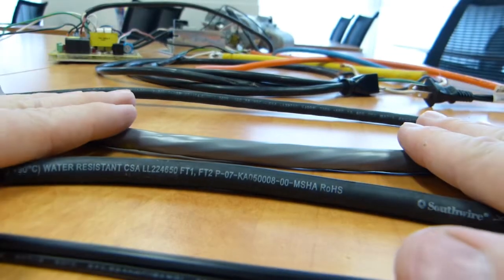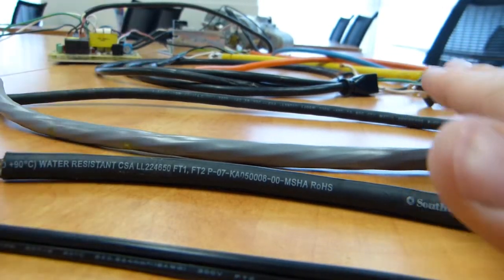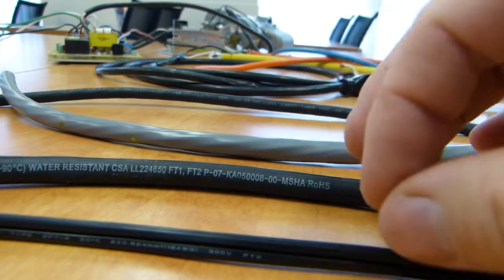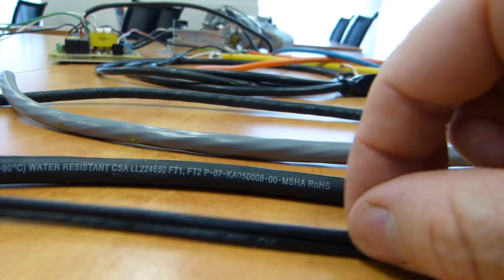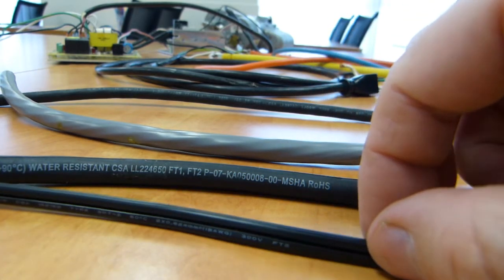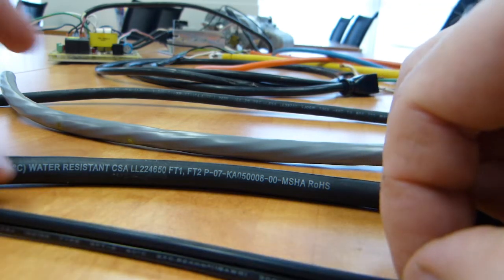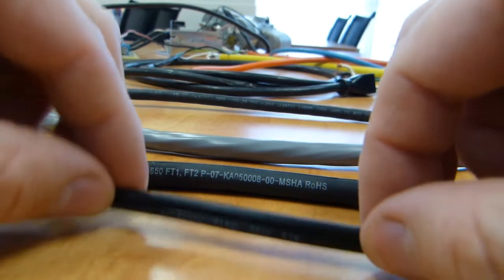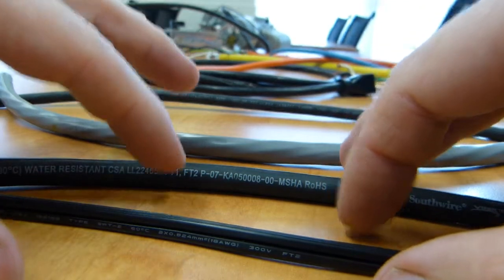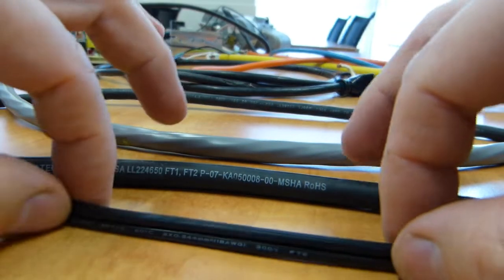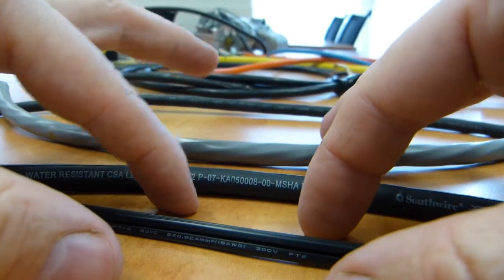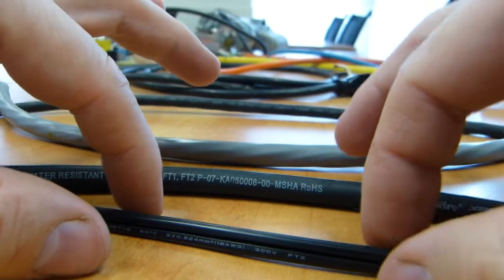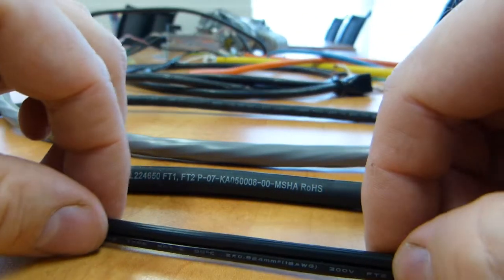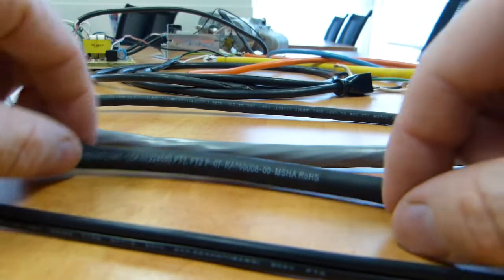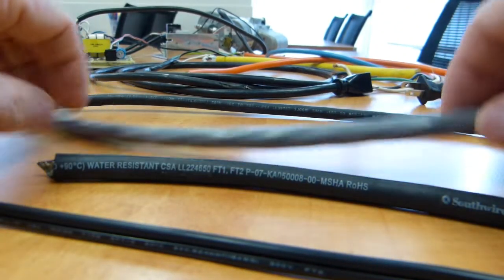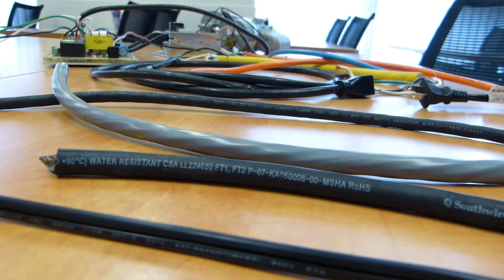So like I said, these numbers are about safety. What kind of safety? This number is the maximum you aren't supposed to exceed when you place the cord on a hot surface or in a hot service environment. So whether it's the surface the cord is on or the air around the cord, it's not supposed to exceed 60, 75, 90, or 105 degrees Celsius.